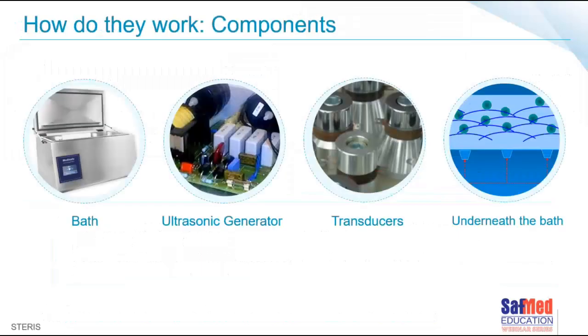You all know, as I do now, that if we don't clean a device properly, of course, we're never going to get the next step of the process effectively done. We're not going to be able to high-level disinfect in some cases, or of course, sterilize those instruments. And that's where ultrasonic cleaners come in. They get into all of these nooks and crannies of these complex pieces of equipment that we just can't get into manually, and sometimes not even get into using a wash and disinfector. So they are a very unique piece of equipment. Well, how do they work?